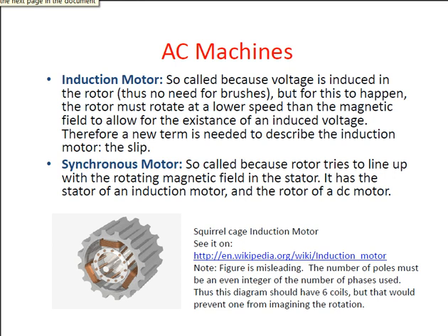AC machines have induction motors and synchronous motors. Induction motors are so called because voltage is induced in the rotor, but for this to happen the rotor must rotate at a lower speed than the magnetic field to allow for the existence of an induced voltage. Therefore a new term is needed to describe the induction motor: the slip. The synchronous motor has a rotor that tries to line up with the rotating magnetic field in the stator; it has the stator of an induction motor and the rotor of a DC motor.